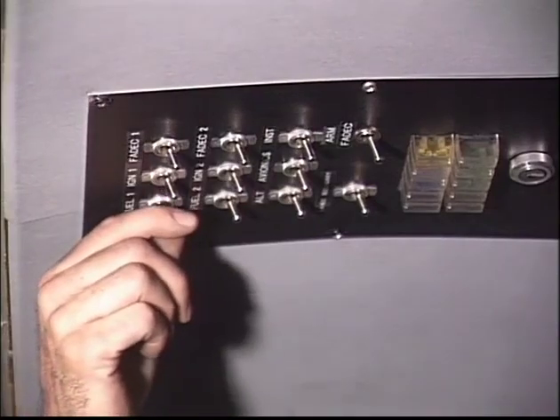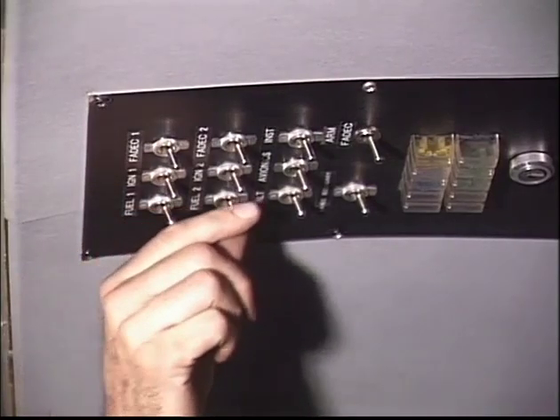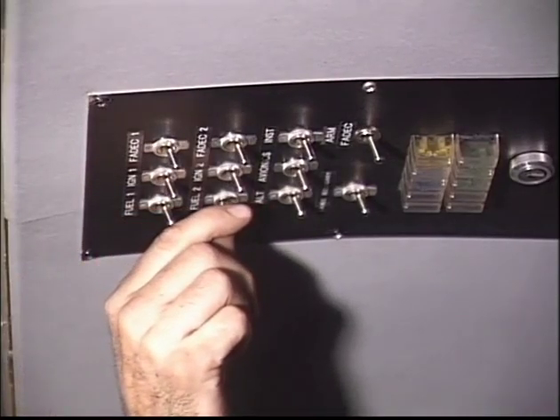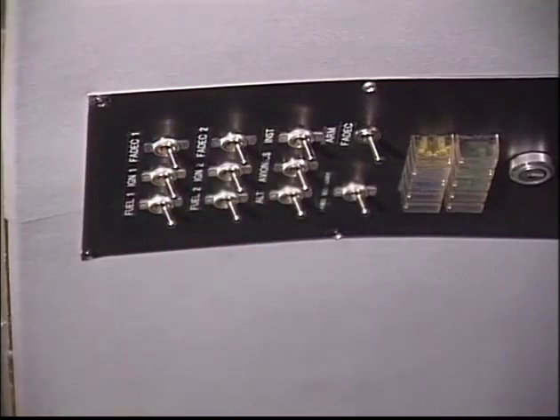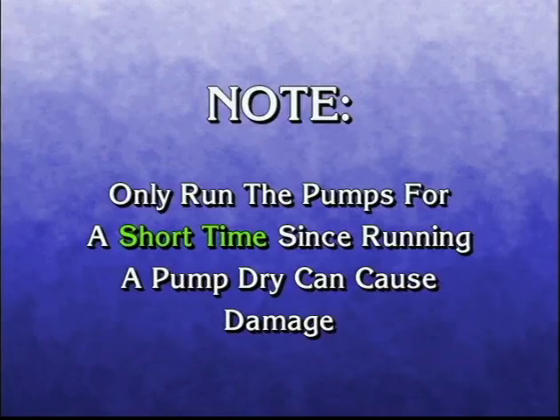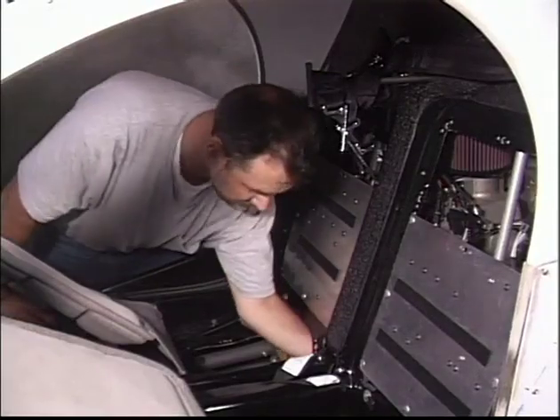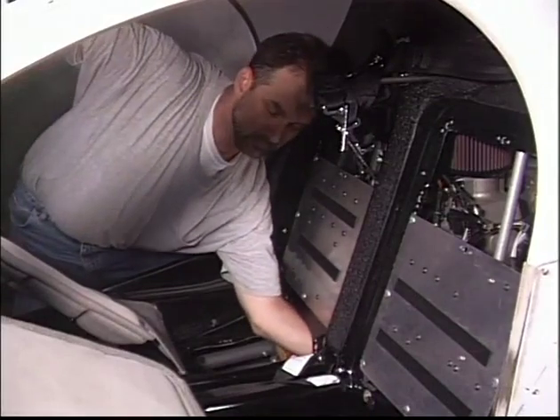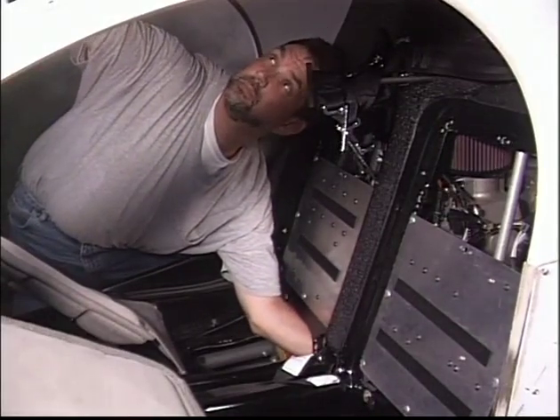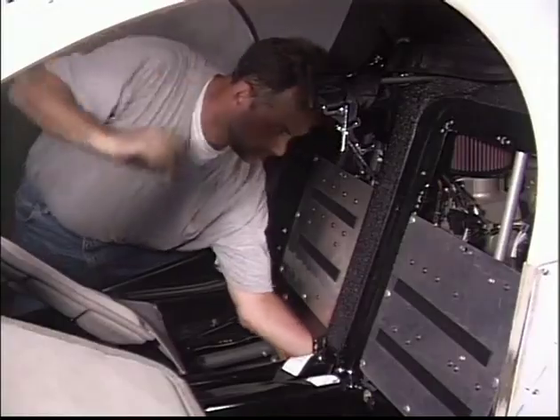Test the fuel pumps for proper operation by turning the switches on and off one at a time. You should be able to hear a pump when it is operating. Only run the pumps for a short time, since running a pump dry can cause damage. Each switch should operate one and only one pump. By feeling the body of a pump, you can tell if it is running or not.